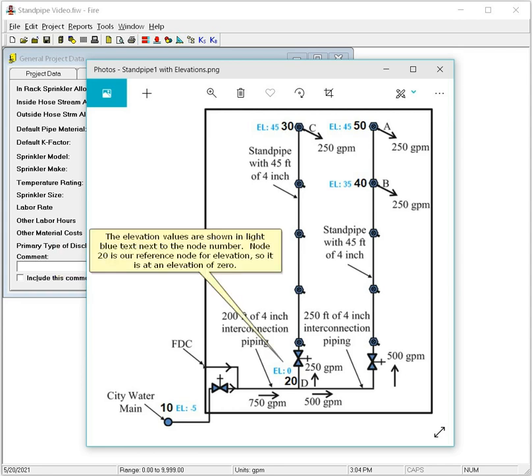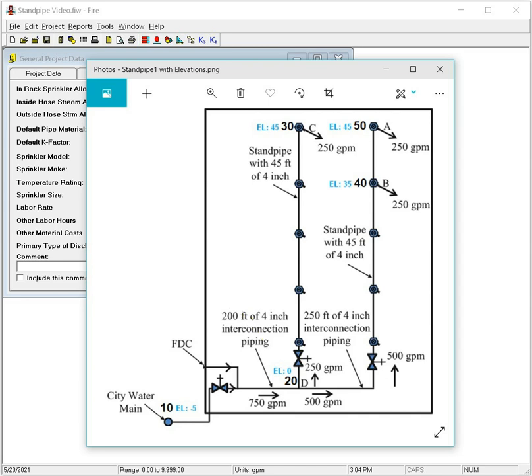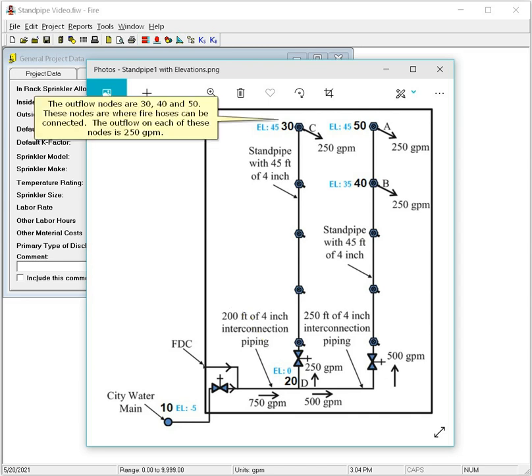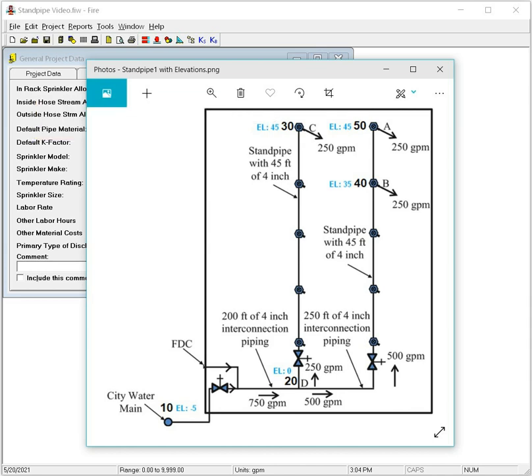The elevation values are shown in light blue text next to the node number. Node 20 is our reference node for elevation, so it's at an elevation of zero. The outflow nodes are 30, 40, and 50. These nodes are where fire hoses can be connected. The outflow in each of these nodes is 250 GPM.